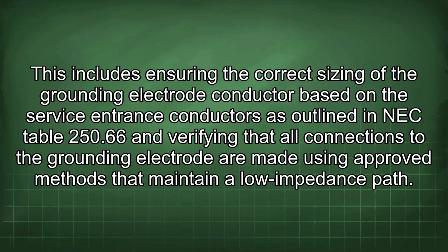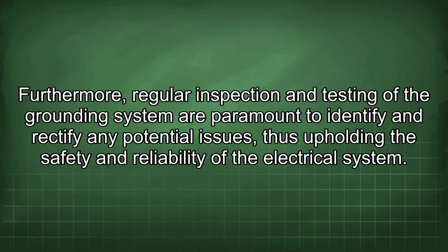This includes ensuring the correct sizing of the grounding electrode conductor based on the service entrance conductors as outlined in NEC Table 250.66 and verifying that all connections to the grounding electrode are made using approved methods that maintain a low impedance path. Furthermore, regular inspection and testing of the grounding system are paramount to identify and rectify any potential issues, thus upholding the safety and reliability of the electrical system.